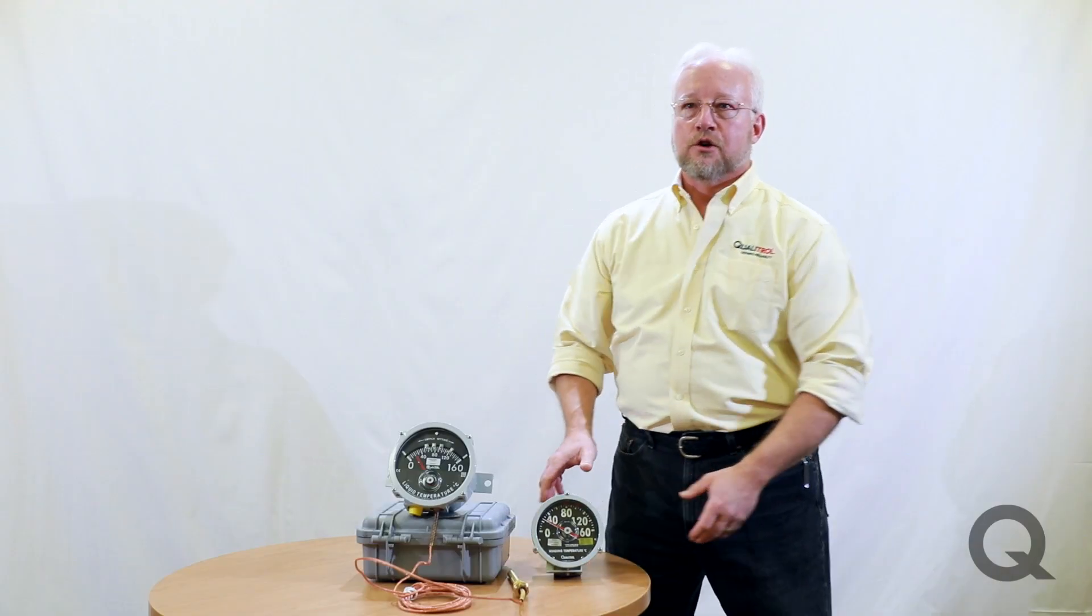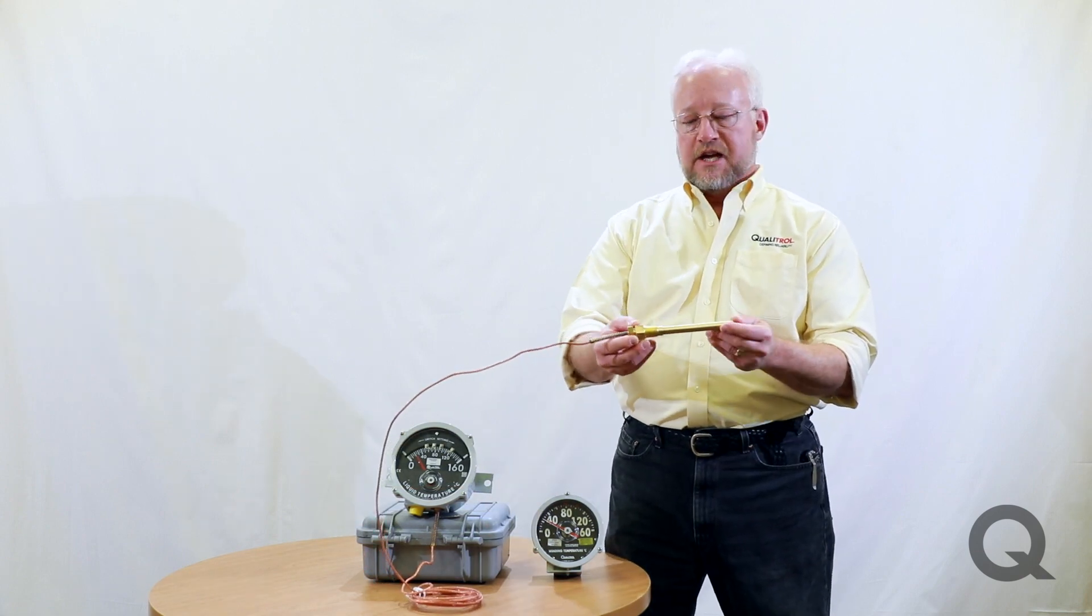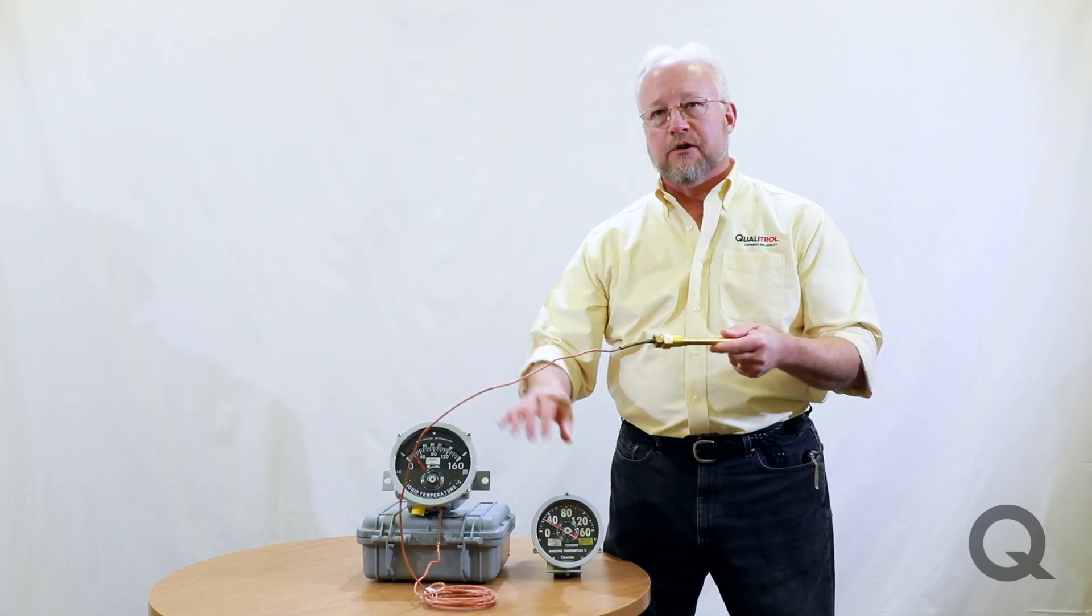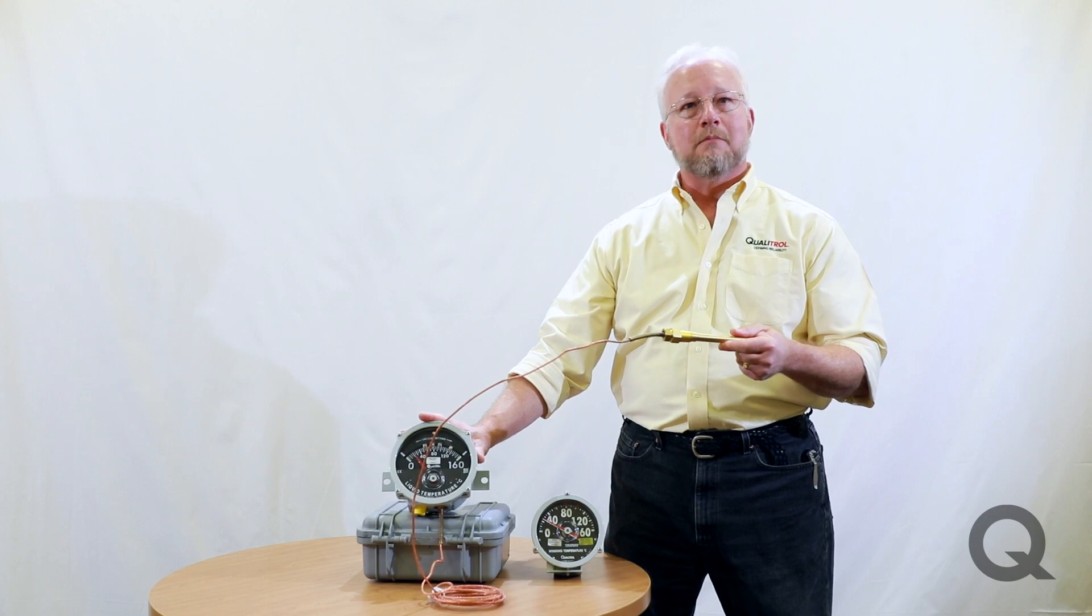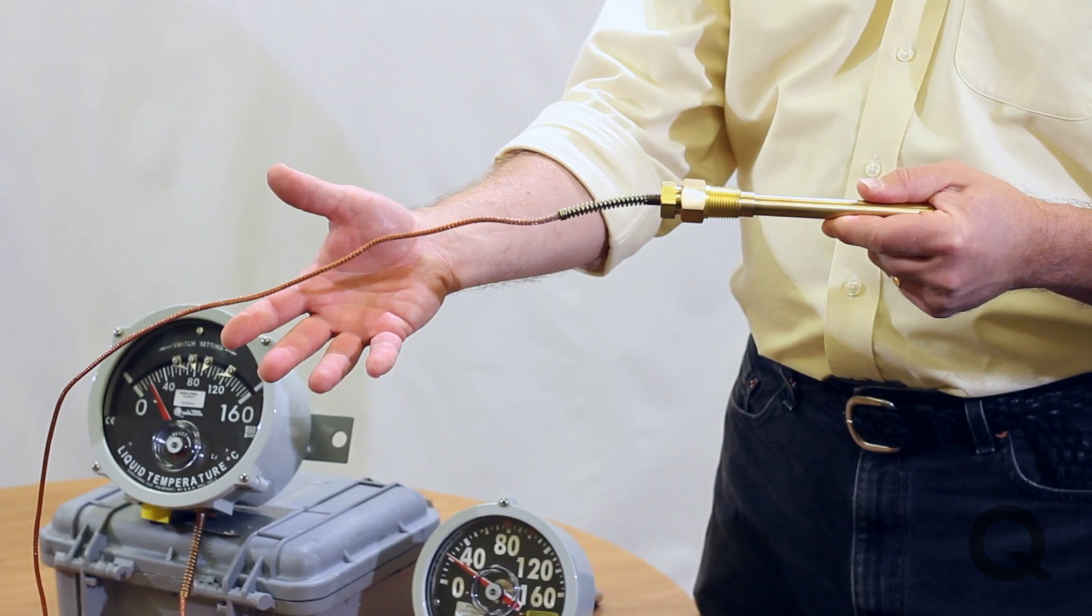On the remote mount, you're going to need to look at the capillary length as well, because this capillary is going to run back to wherever you mount the thermometer. If the capillary is too short, you've got a big problem.